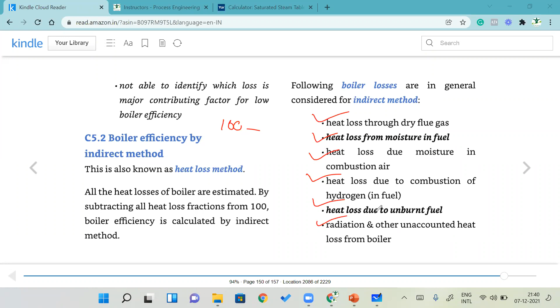And heat losses due to combustion of hydrogen. If there is hydrogen in the fuel and it is burned, that forms water vapor. So again, that is a problem. Heat loss due to unburnt fuel. If the fuel is not burned well, that is again inefficiency. And the radiation and other unaccountable losses in the boiler. So when I'm talking about the direct method, I don't know what the losses are. But when I'm talking about the indirect method, these are all the losses. If I can prevent these losses, automatically I can increase the boiler efficiency. Now we will look at them one by one.